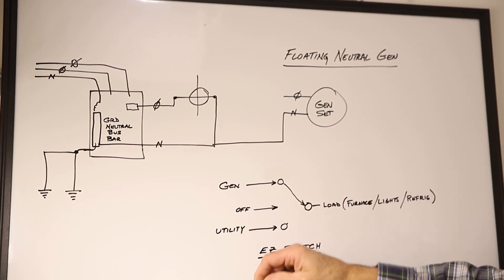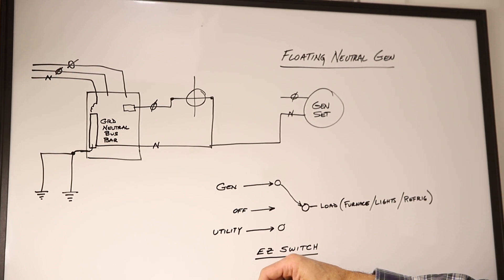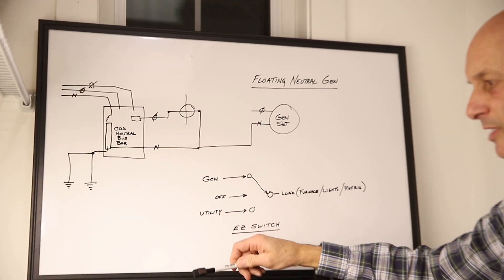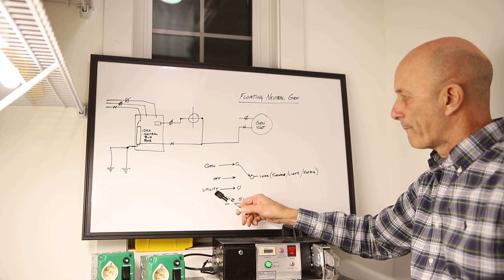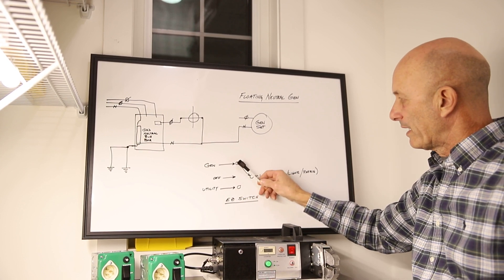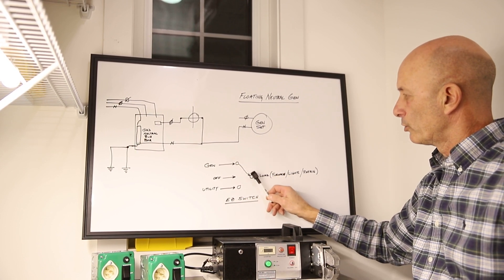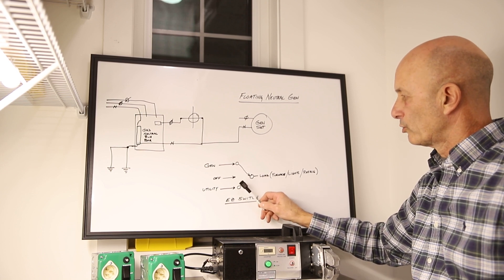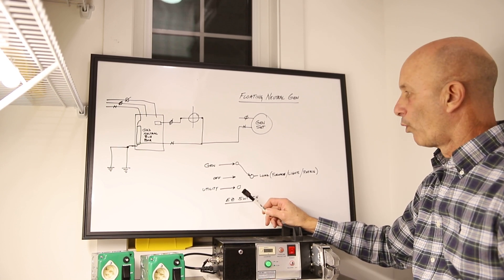So this is why a switch that has a label on it, a standard that meets a UL standard will not back feed. You can only be from the load to the generator, load to off or load to utility. You can't be in more than one.